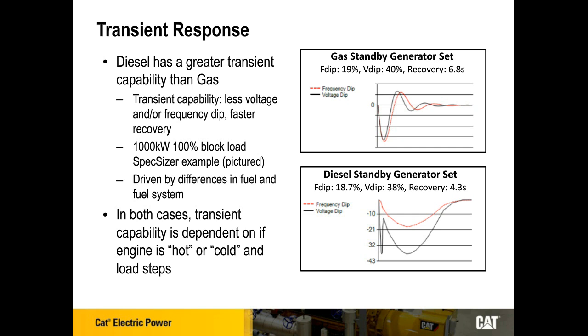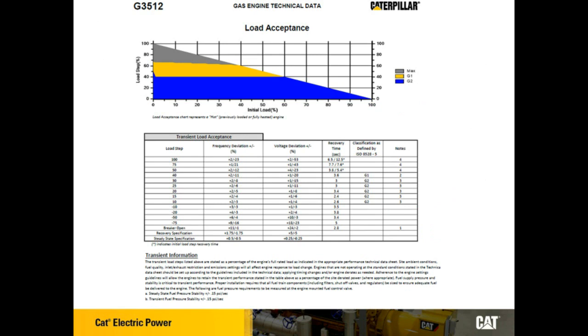So if we take an example of a 1 megawatt standby gas generator set from Caterpillar, in the performance data sheet there's a page that includes load acceptance data. I just wanted to briefly talk about this to make everyone familiar with it, so if you're looking at a project down the road, you can quickly see how to compare the performance of gas and diesel and see if the gas might work well for your situation.